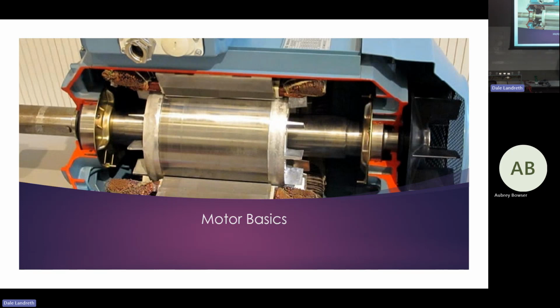This goes back to being a technician. We record our annual log sheet. Let's say I did the annual in 2022 and did a mega ohm test on this motor. I go back in 2023 and do another mega ohm test. What does that tell me? If those windings have degraded over that time span. So what would we expect a mega ohm test on a brand new motor to be?